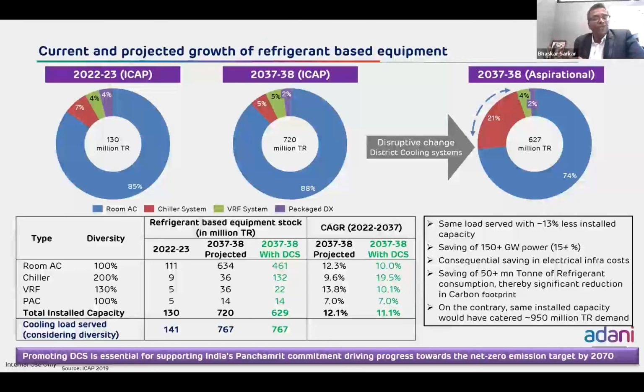So if we look at this graphs, these are few numbers which are also taken from the ICAPS, and then we have projected DCS onto it. The green numbers are DCS. So if we see the projections of various types of air conditioning methodologies over a period of 2023 to 2037-38 as projected in the ICAPS, we can see that the room AC growth is almost growing at 12%. The chiller growth, which is the primary ingredient for a DCS system, is expected to grow at a meager rate of about 9.6 or 10%. VRF is expected to grow at 14% and PAC 7%.